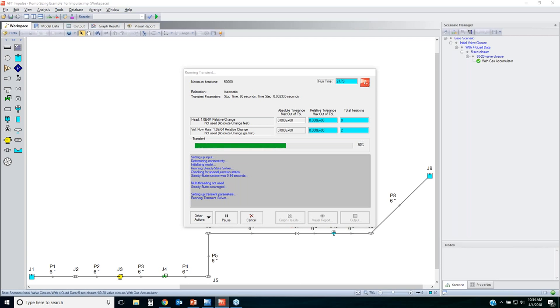A good question came in: how do you find four-quadrant curves when suppliers usually don't supply them? You're right — a lot of pump manufacturers don't publish four-quadrant curves because they don't like to test their pumps under those bad conditions. If you want one, you'll probably have to pay for it. In Impulse, we have 21 different four-quadrant data sets based on different specific speed values from a variety of references. If you don't have any other data, using one of those data sets is the best way to get something reasonable.